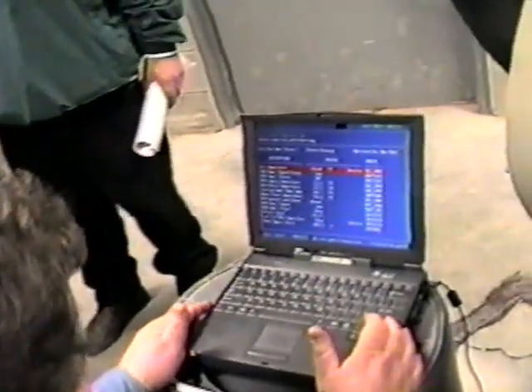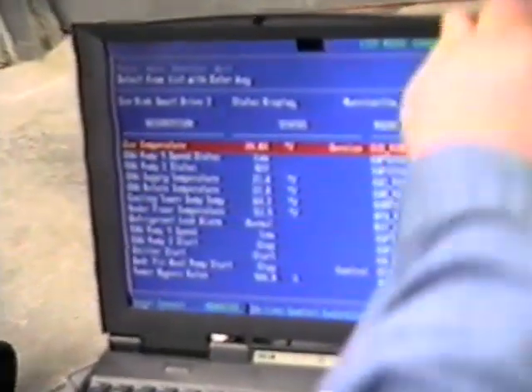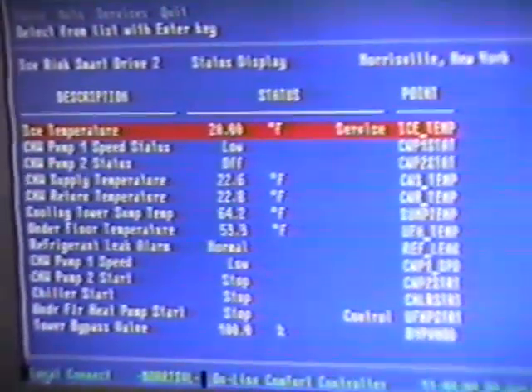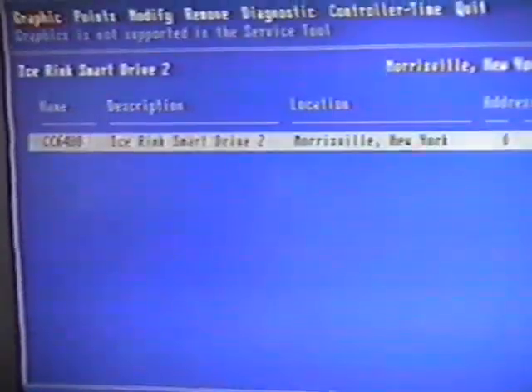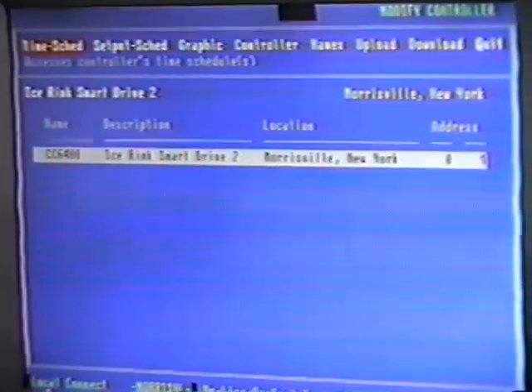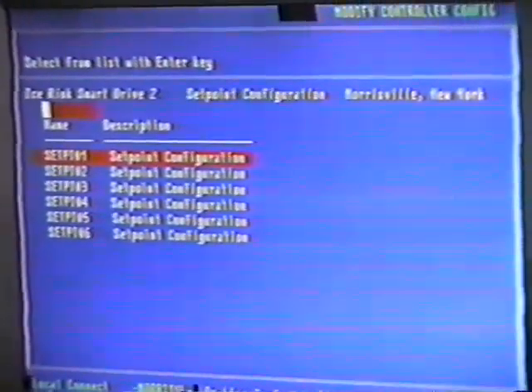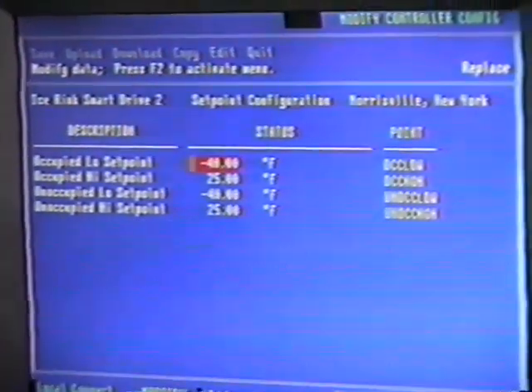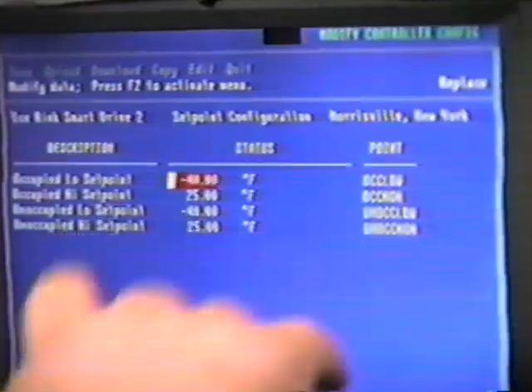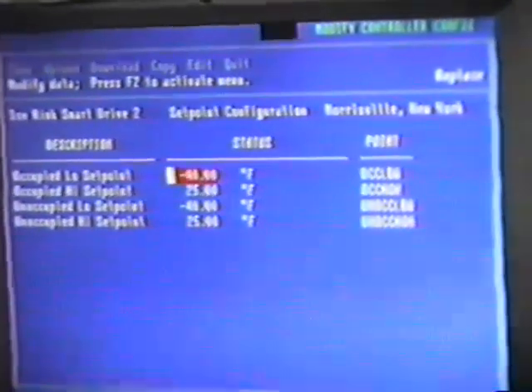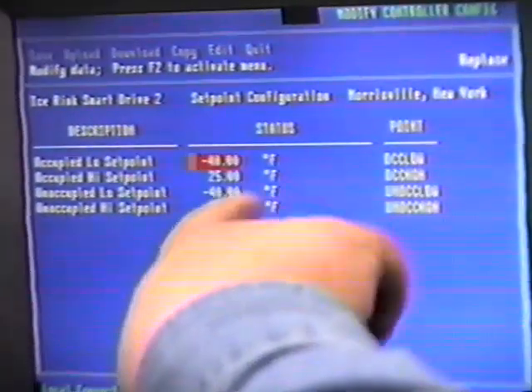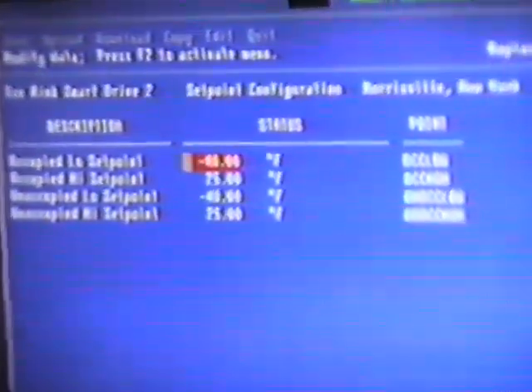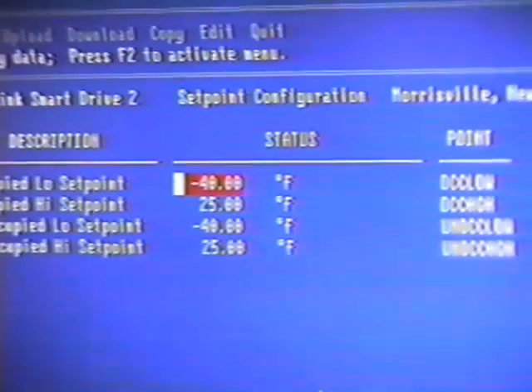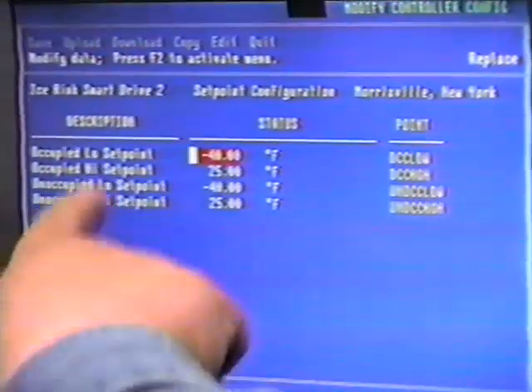Okay, let's see. Refrigerant leak normal. Now it was calling for the chiller. Okay, it stopped here. So let's see. We went to this, my chiller set point. You should get a similar schedule on this once I get you rigged up. There are two sets of set points. One of them, as on this one, will be -40. It doesn't concern us. It's basically the heating set point. All we want is the cooling, which is always the high.